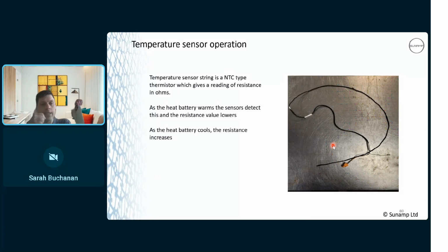So your temperature sensor, it's of an NTC type, which gives you a resistance reading in ohms. As the battery heats, the sensors detect the heat, and then that resistance value lowers. So when the battery's cool, across the three sensors, we'll have about 12 kiloohms.